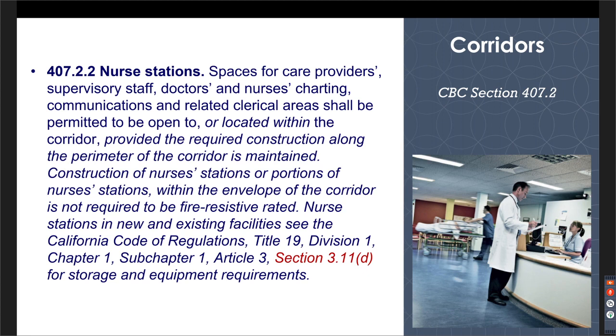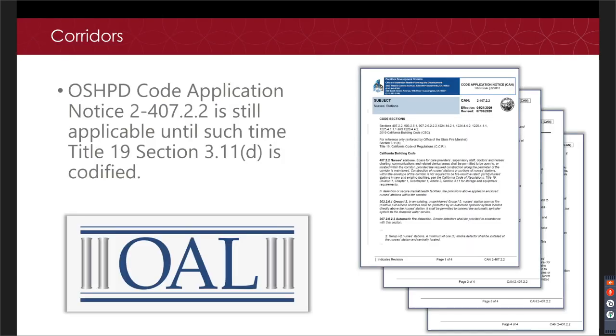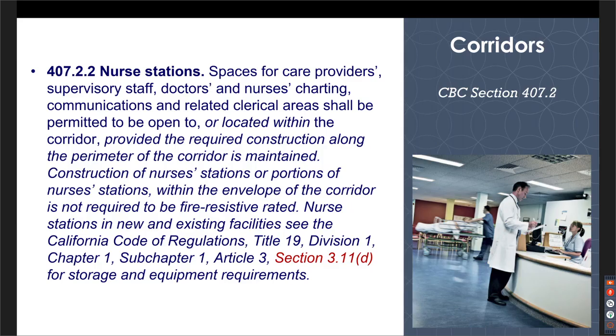Another area that can be open to the corridor with certain criteria in place are nurses' stations. So those nurses' stations can be open to the corridor, and then there are certain items that can be in that nurses' station, and they'll have smoke detection that's required, centrally located, above that nurses' station. And then, of course, if it's sprinklered as well. And we have a CAN, and for those who aren't familiar with the CAN, it's a code application notice that specifically states what could be in that nurses' station. You know, what size fridge, the chairs, computers, etc., paper. This language will eventually make its way into the code, but in Title 19, I went backwards for a minute here. Title 19 in Section 3.11 is a section that says that there's no storage in the corridor, the required width has to be maintained, etc.